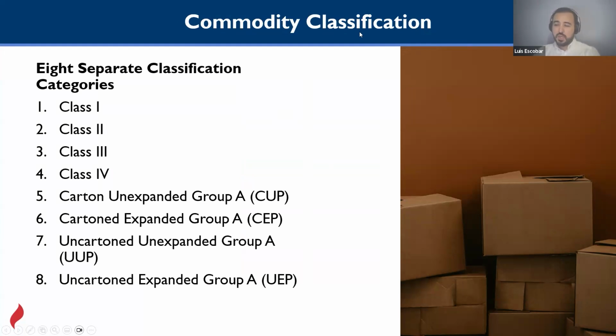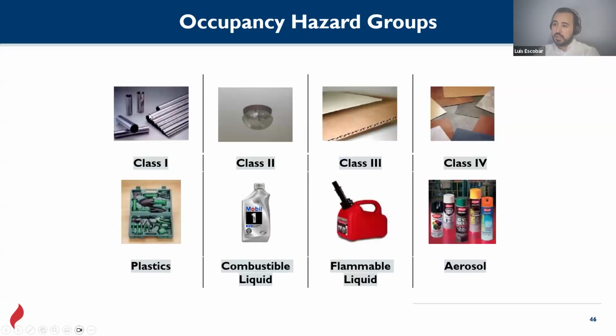We were talking about the combustibles and the heat they release, and they can be categorized in class 1 through 4, carton unexpanded group A, uncarton unexpanded group A, uncarton expanded group A. The group has to do with the type of plastic. There are 3 groups of plastics for NFPA, A, B, and C, depending on whether it's PVC, polyethylene, or PET. We have a couple of examples here. Class 1 goes from the lower group to the higher or most dangerous group. From 1 through 4, progressively they increase the heat release of each one.